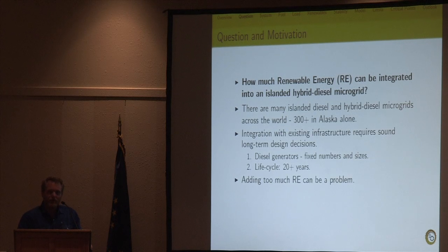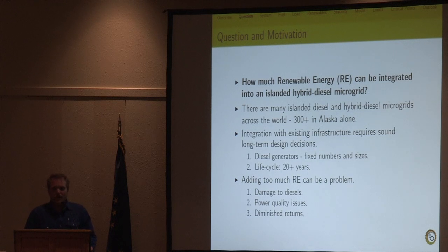Adding too much renewable energy can be a problem. For one, it can damage the diesels by having too much ramp rate or too low a loading, depending on how you're operating your plant. You can also damage all kinds of other equipment due to power quality issues, and on top of that, potentially your reputation by having too many blackouts, and at the same time you would then damage your bottom line.